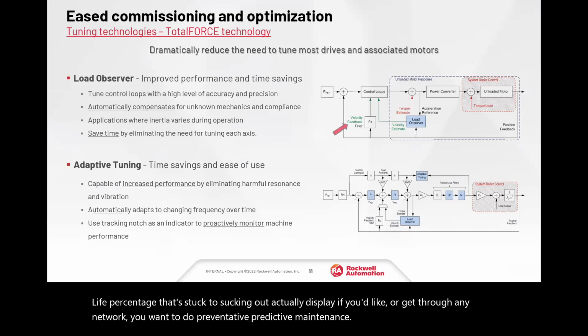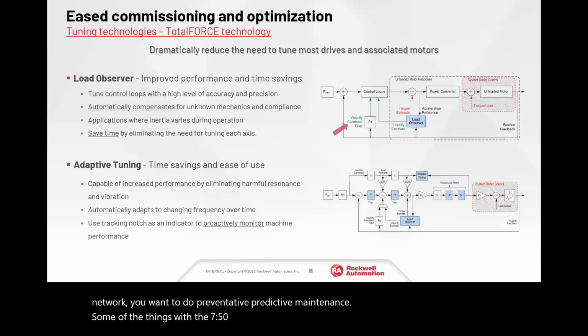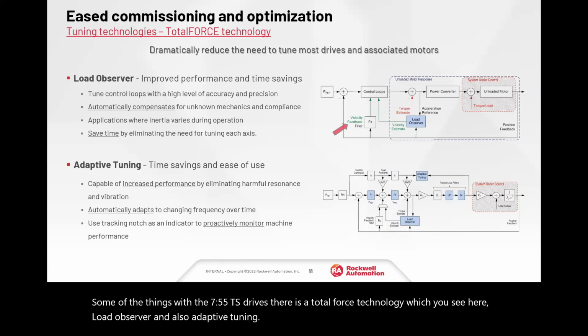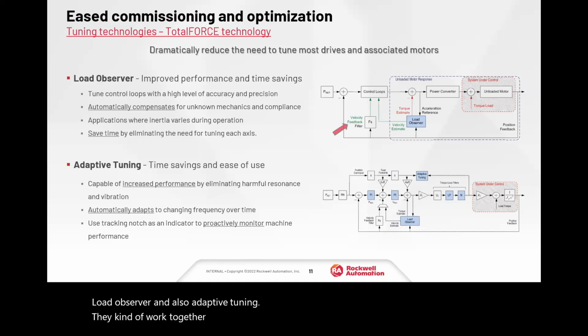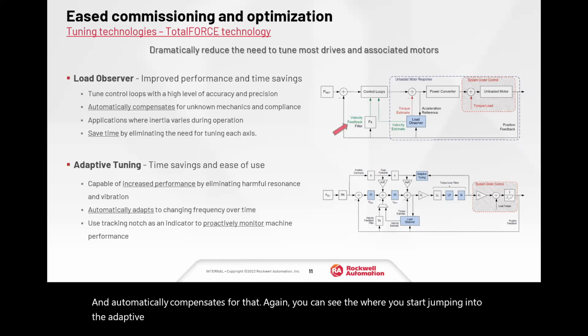Some of the things with the 755 TS drives: there is Total Force technology, which you see here, load observer, and also adaptive tuning. They kind of work together. The load observer actually identifies the load, changes in the load, and automatically compensates for that. Again, you start jumping into the adaptive tuning. This actually proactively tunes the drive on the fly.